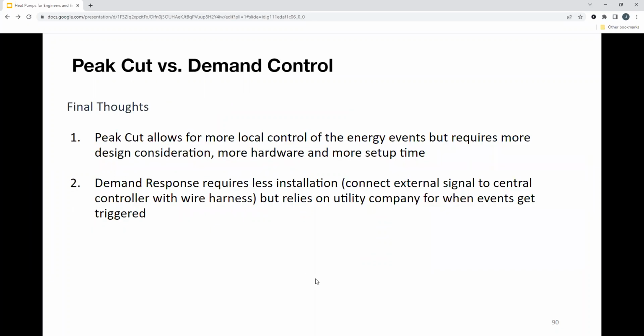Basically, a quick comparison: peak cut allows more local control. An owner or a facilities manager can take part in these energy events to reduce the kilowatts on their own time, right? It does include a lot more design consideration, hardware, and time to set up. Whereas demand response is less installation. All it is is an external signal connected to the outdoor units. But it does rely on the utility companies for the event. So utility companies will turn it to 50%, and then you might not get the capacity that you need at certain times during the day. But these are both options you can use for saving energy at specific times.